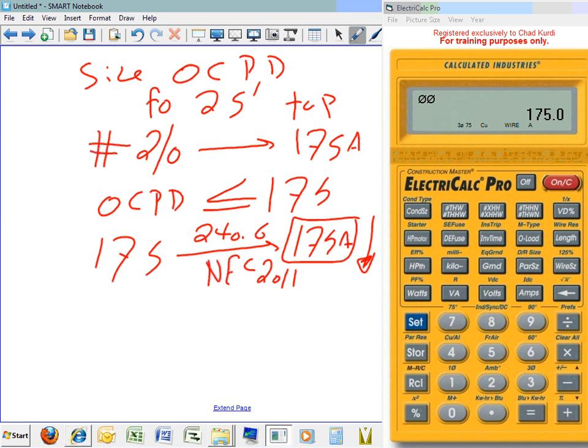So it's just coincidental that it came out to a standard. Absolutely, it's coincidental. This could have been 173. Then you have to go down to where? 150, right? The next standard down is 150. Had this been 171, I can't go to 175. I have to go down to 150.